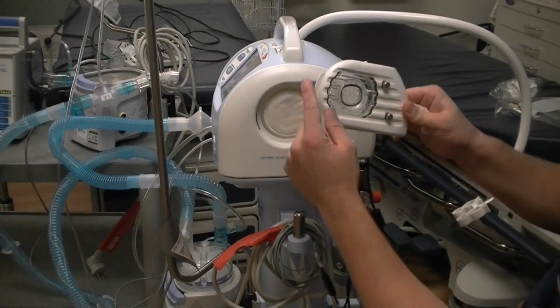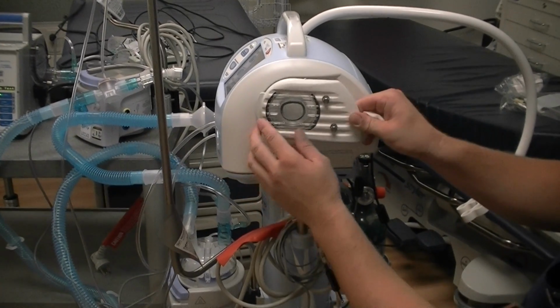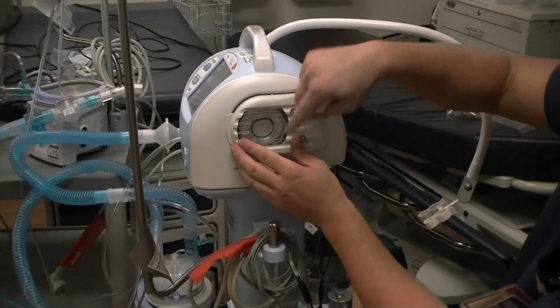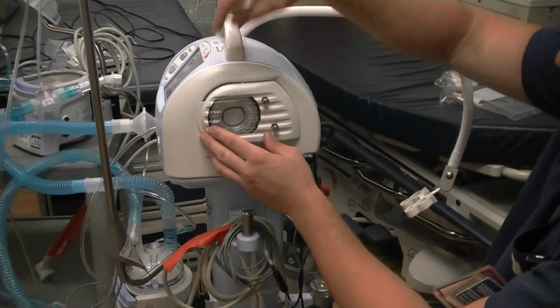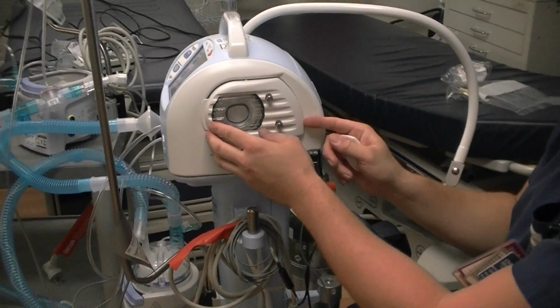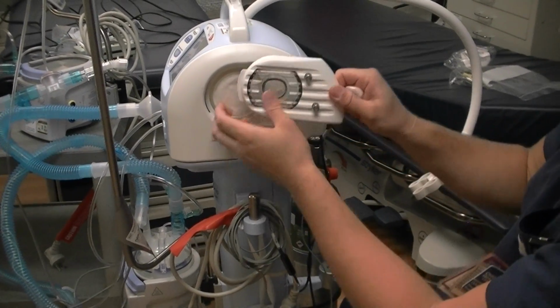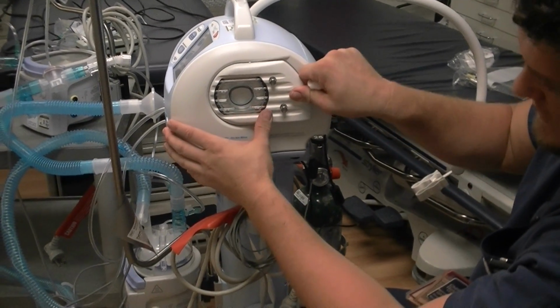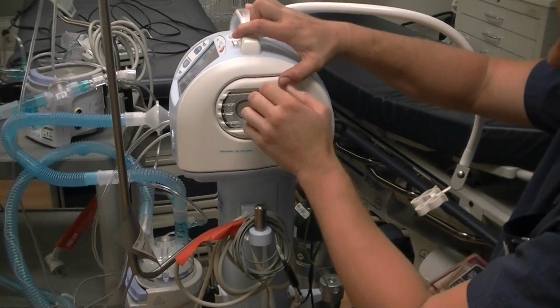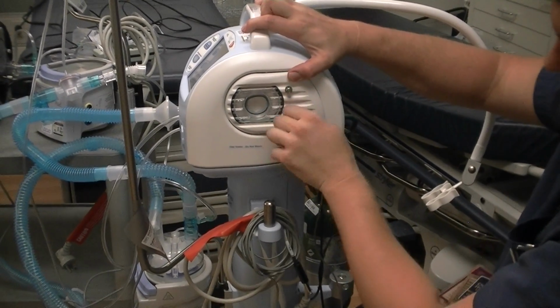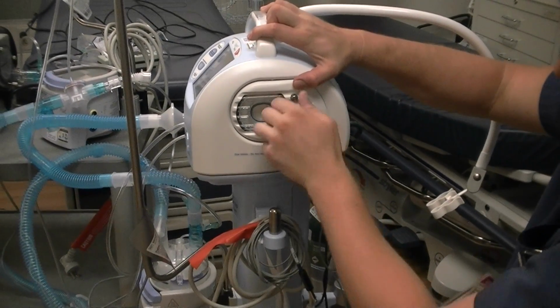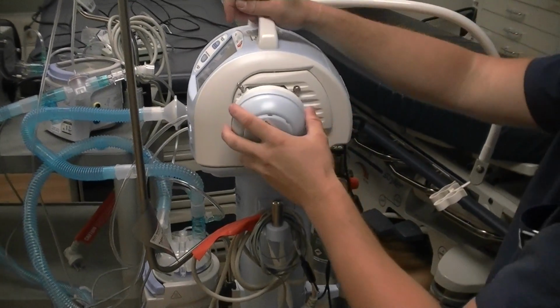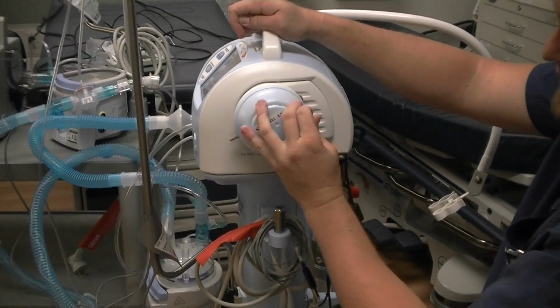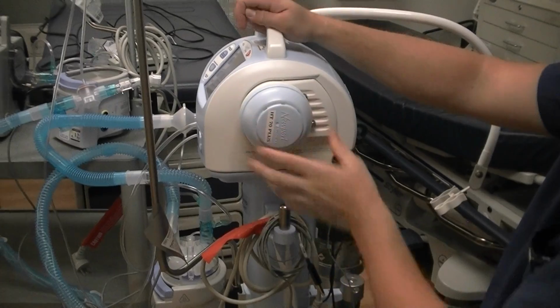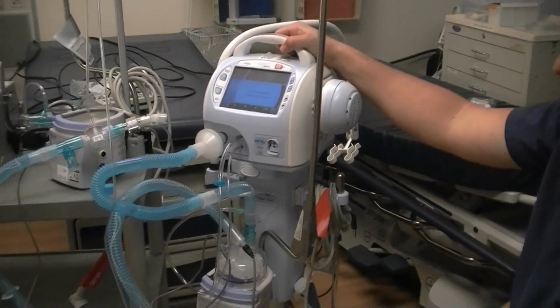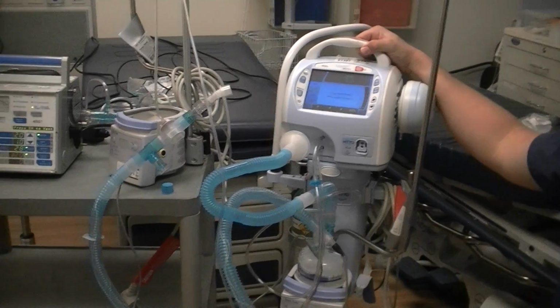Now when you stick this back in, this piece has to go in here all the way. If it's sticking out like this, these will still screw on, but you're going to have external airflow coming in through here. You won't get your correct O2 percentage that you're looking for. So make sure this area right here is in tight, and simply screw this back on. Grab your low flow O2 or blender, and usually all these have some kind of screw-on mechanism. And we're all set to go. And that's the HT50 and the HT70 setup. Thank you very much.